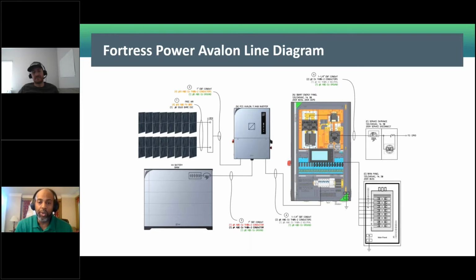So you don't have to now wire a second sub panel, if that was the case. So when you have a 200 amp pass through, it allows you not to have to wire a secondary panel, and you're able to really manage your circuits because the relays are now allowing you to shed the load. So when he had mentioned the appliance circuits, or you're talking about your power circuits, we're really talking about single pole breakers, right? So your single pole breakers typically are going to be your 20 amps.